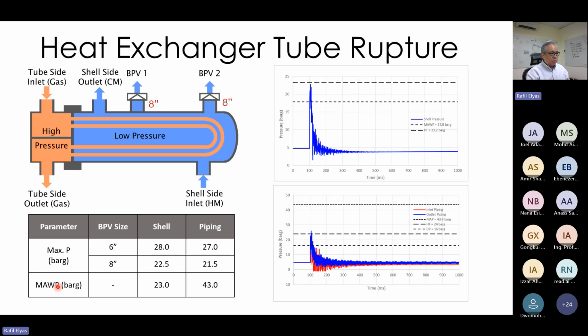So this is what we were looking at from this analysis. We had a buckling pin valve over here, and one located over here. Initially, in terms of sizes, we looked at a 6-inch, and we found that with the 6-inch system we had some issues. It was not acceptable. We were going past the maximum allowable working pressures.